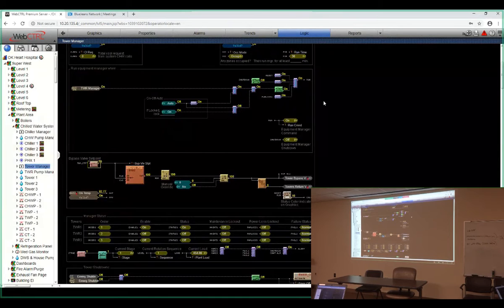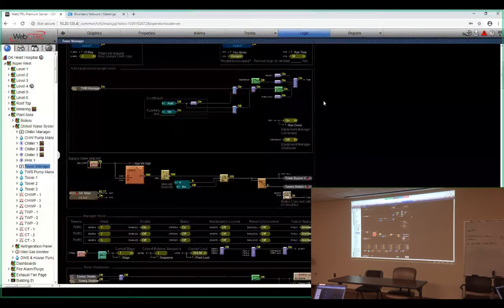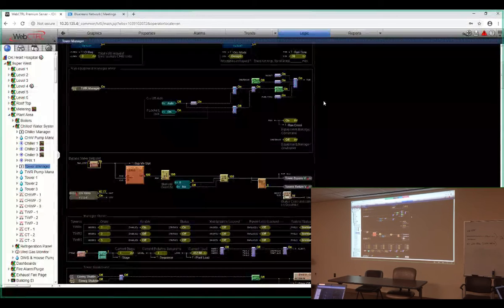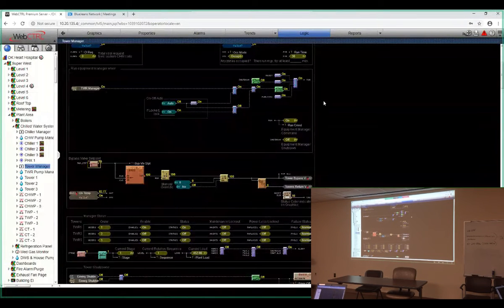And I'll say it again, the chiller manager is what initiates the chill water system. And then each component has its own manager. So the towers have a manager, the pumps have their own manager, but the chiller manager initiates the call. So it's kind of the master controller for all of the systems. There's actually only 2 controllers doing all this, one for the towers and one for the chillers, but all of those signals are managed by the chiller manager.